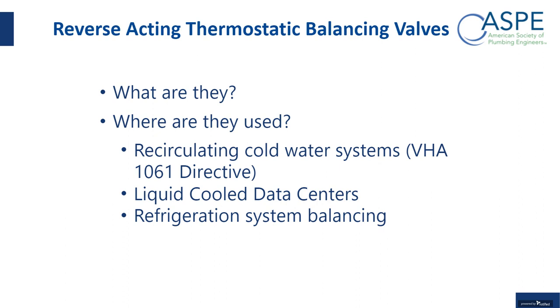So next, and I know we're running out of time, so I'm going to go through this really quick. There's also what we call a reverse acting thermostatic valve on the market, and that acts just the opposite of a direct acting, which is what we've been doing for hot water systems. These valves will close on cooling water, not close on warming water. So they're used in cold water systems. They're used for recirculating cold water systems.